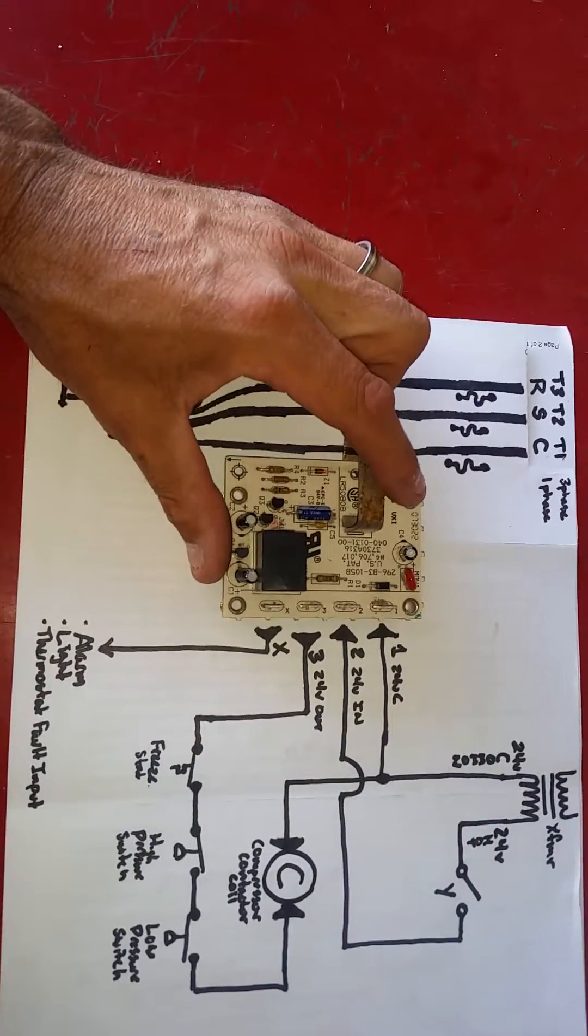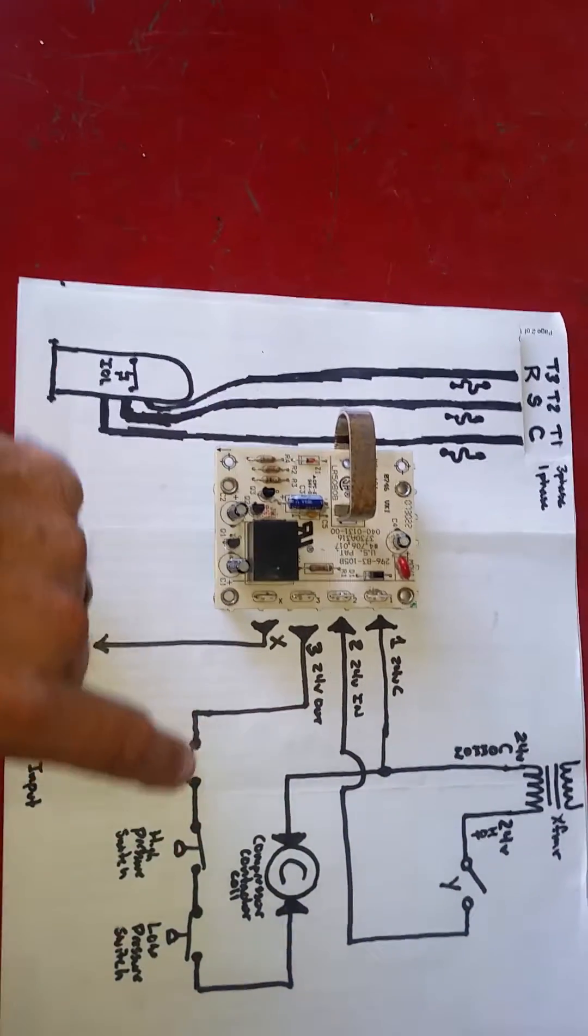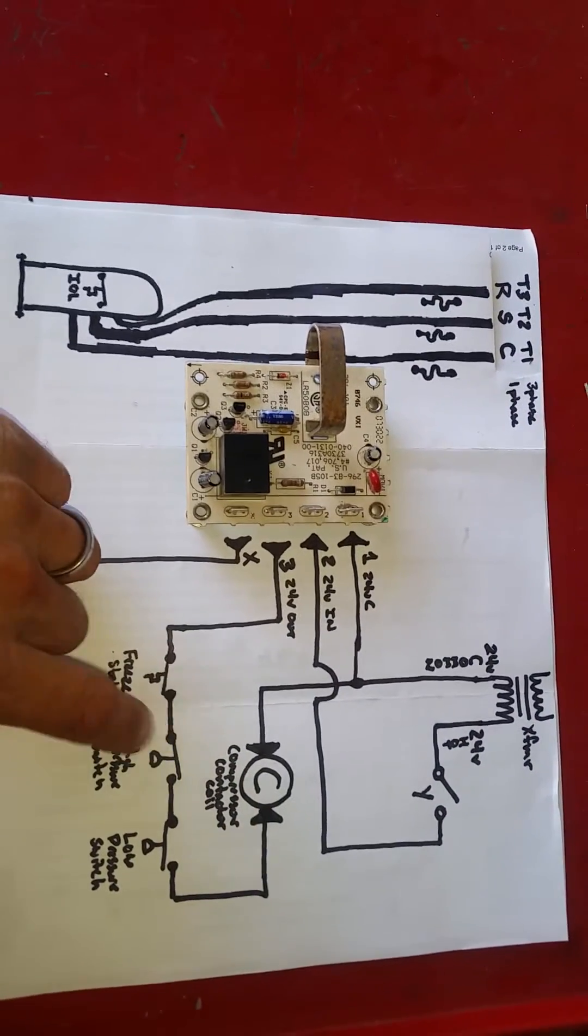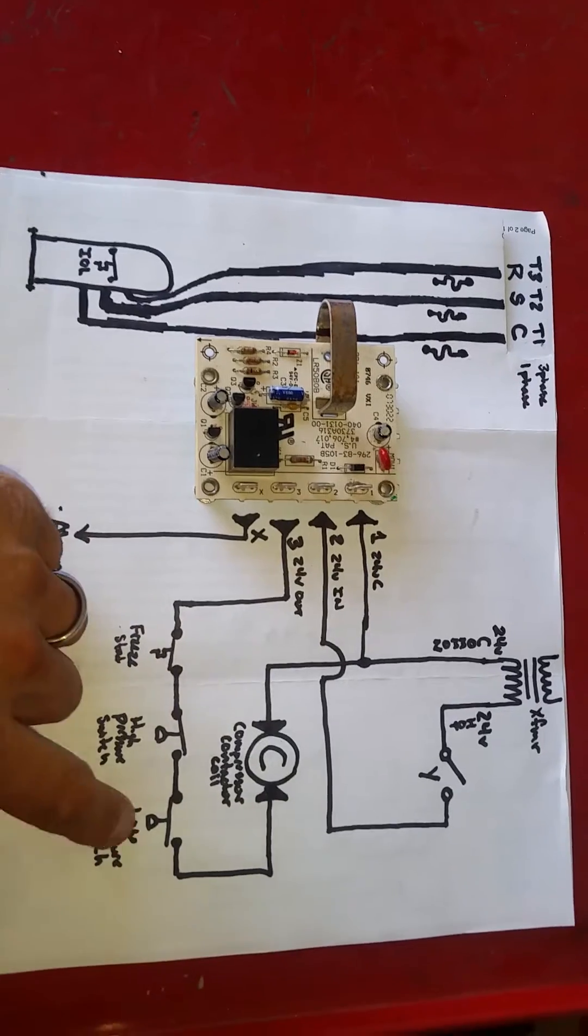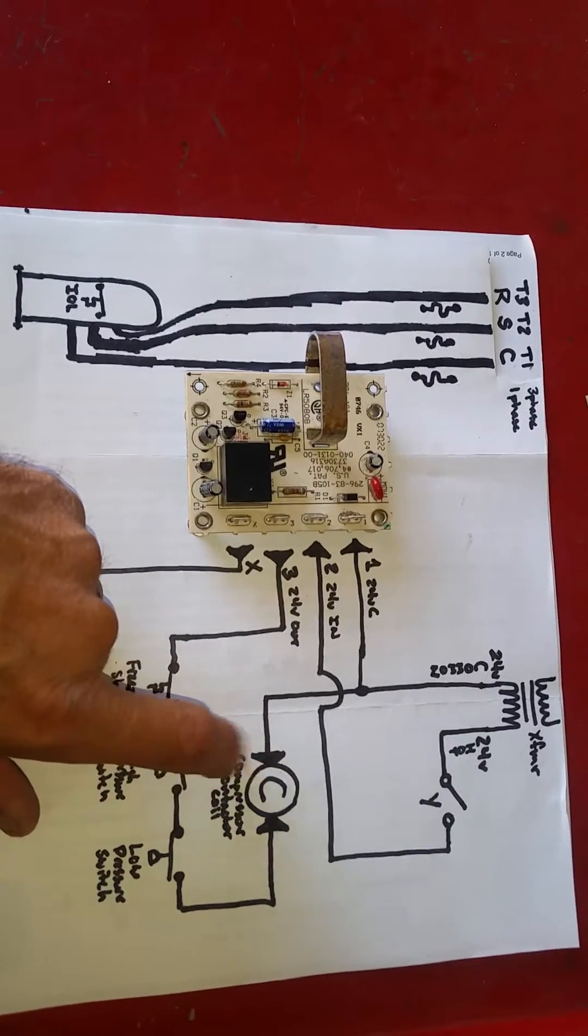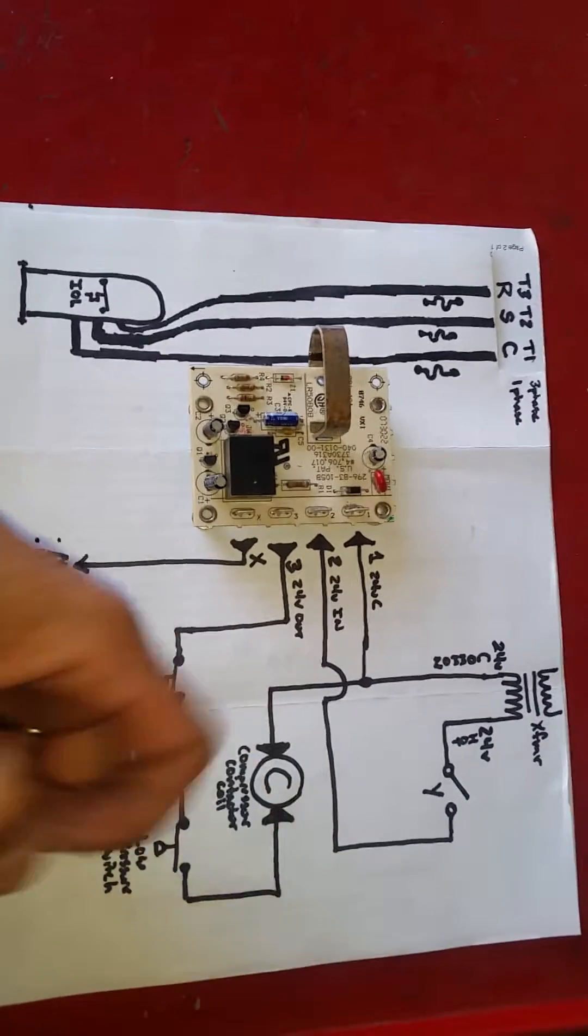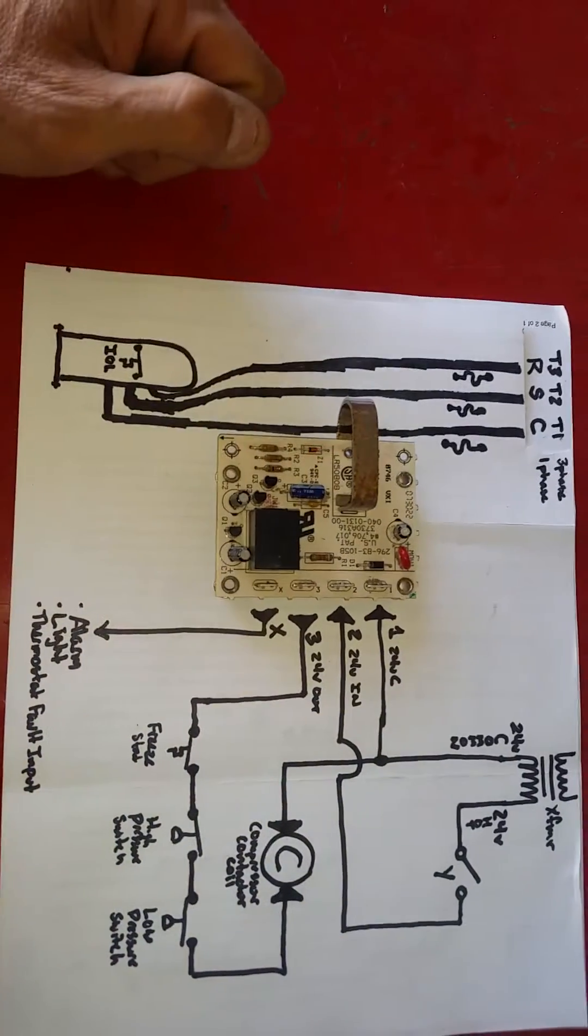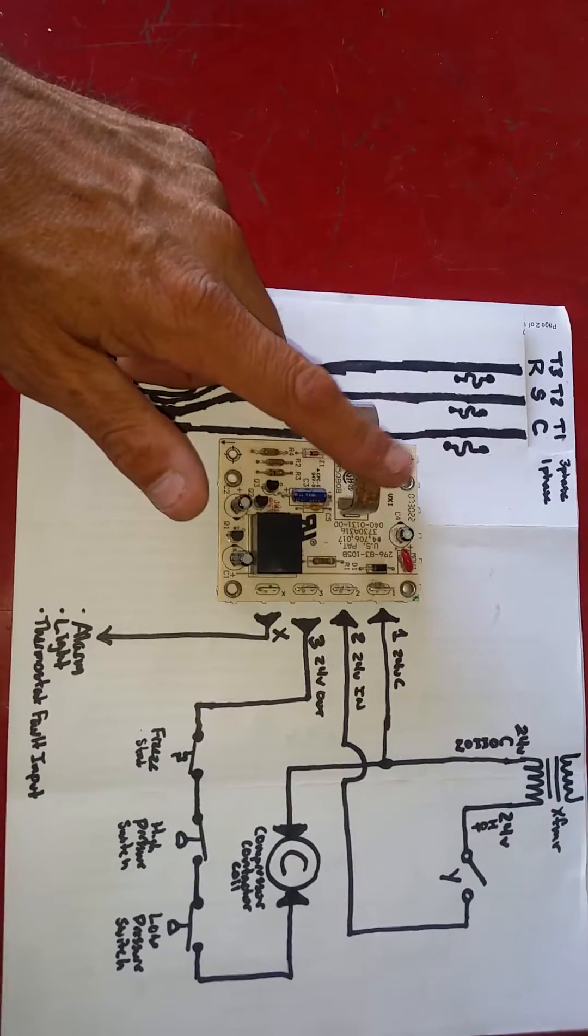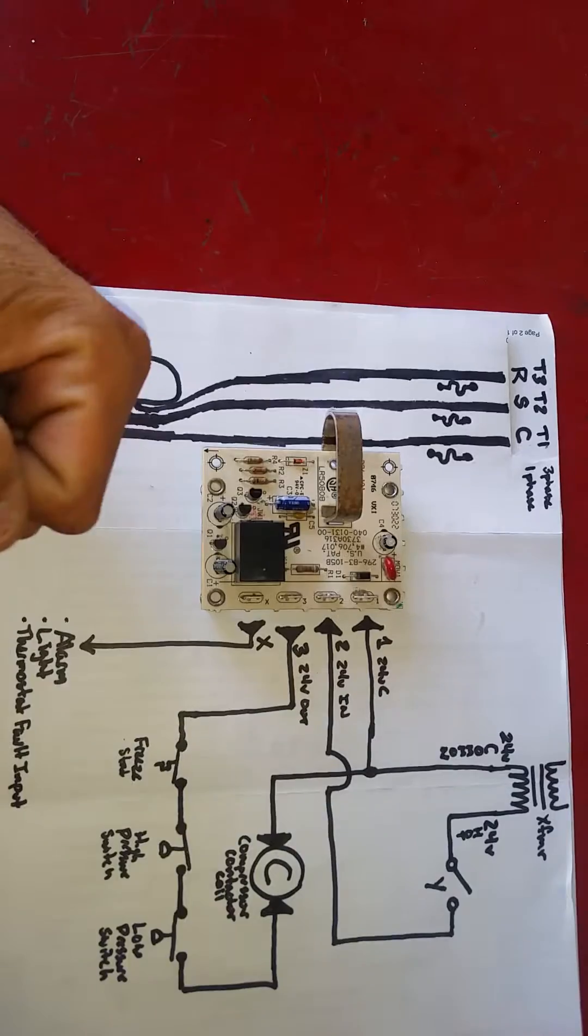The reason why I call this a current lockout is because everything relies on current. It has nothing to do with the safeties. If a safety was to open, whether or not the freeze stat, a high-pressure switch, or a low-pressure switch was to open, all it's doing is killing the 24 volts to the compressor contactor. Because the compressor contactor opens, we no longer have current at our compressor. And because we have no current, we drop below that 0.5 amp threshold. The current sensor recognizes that and opens that relay and kills power to the entire system.